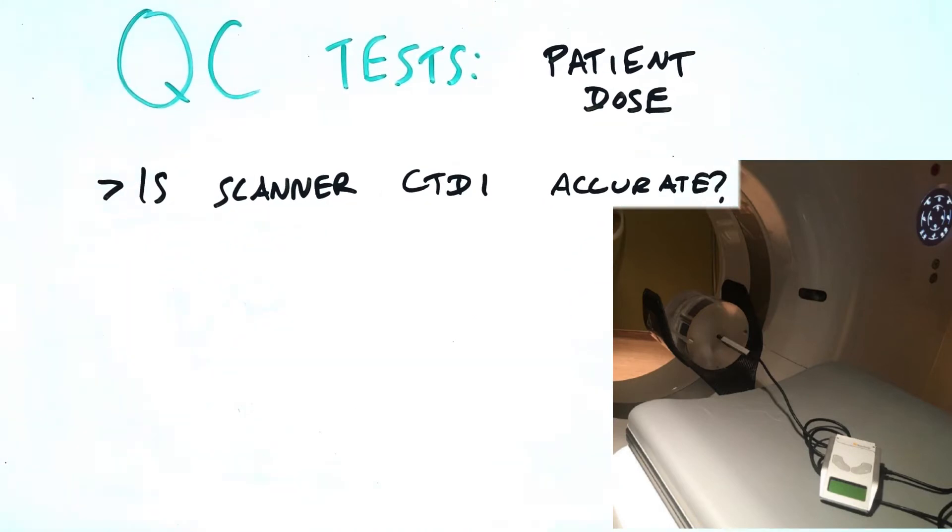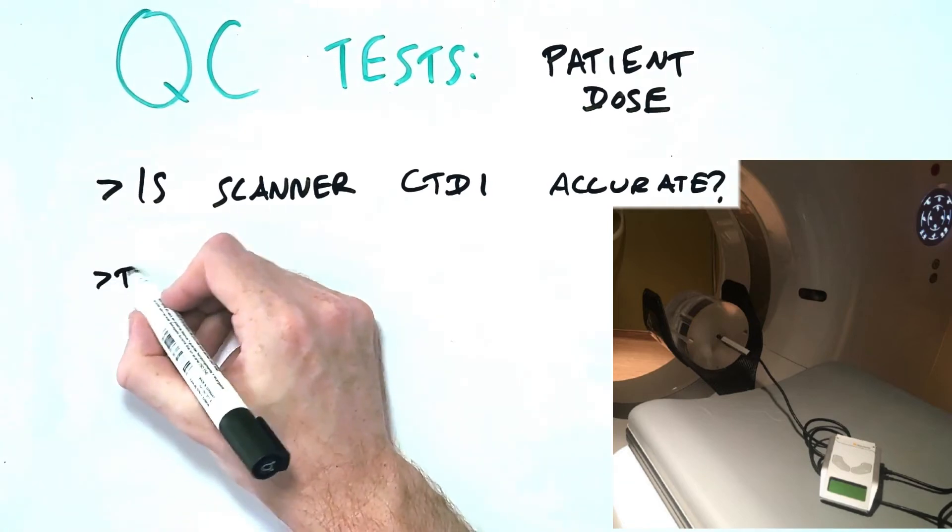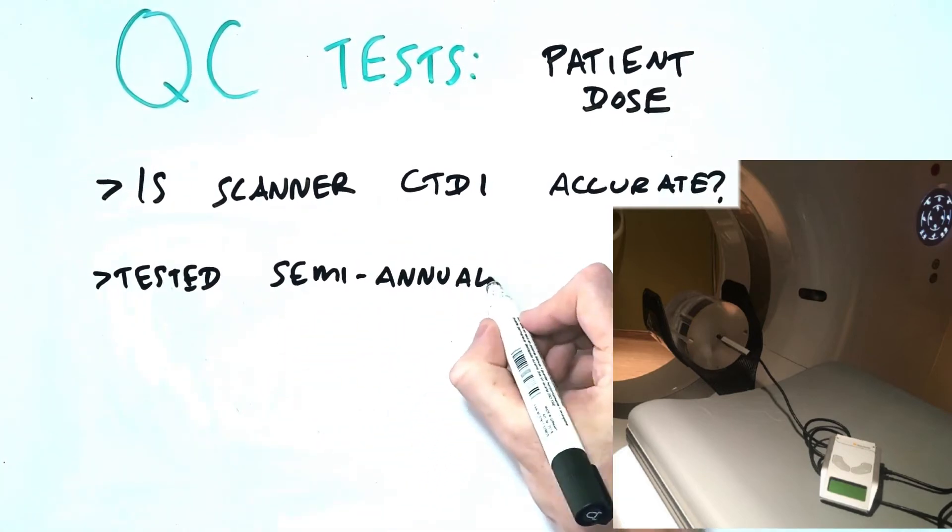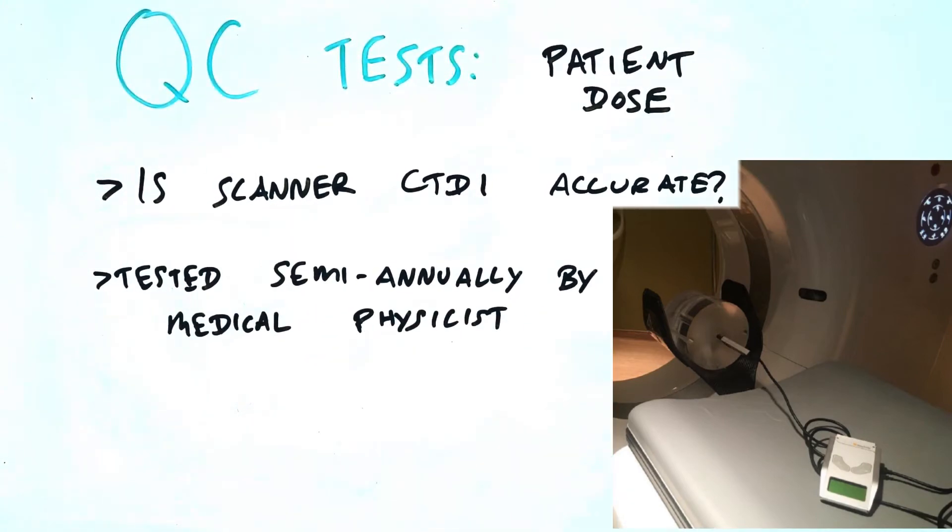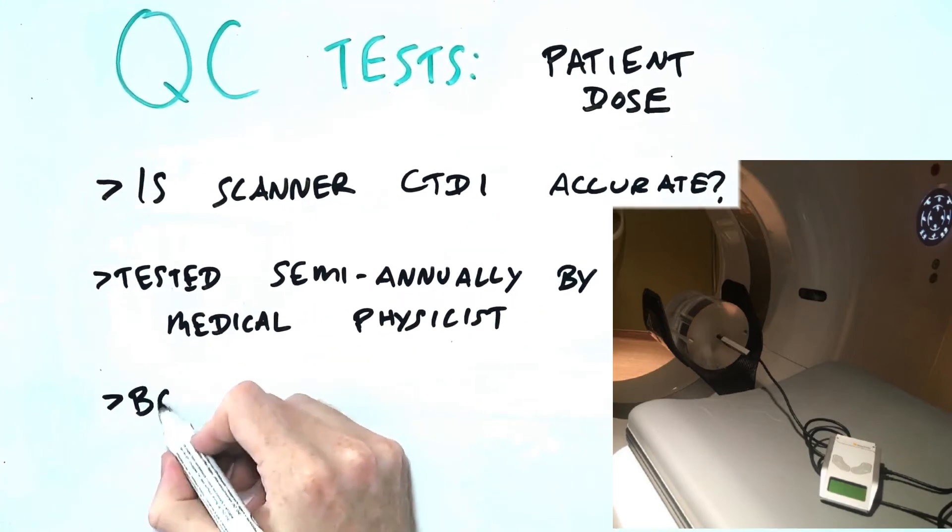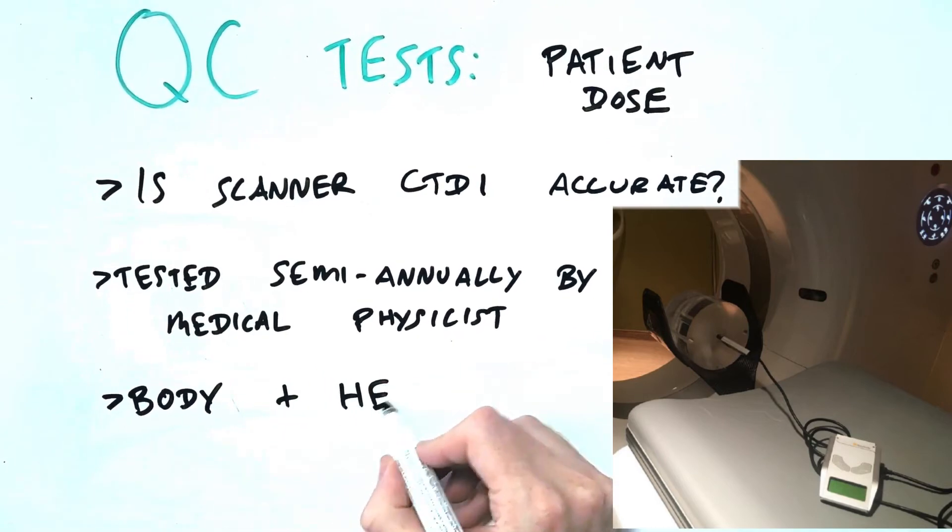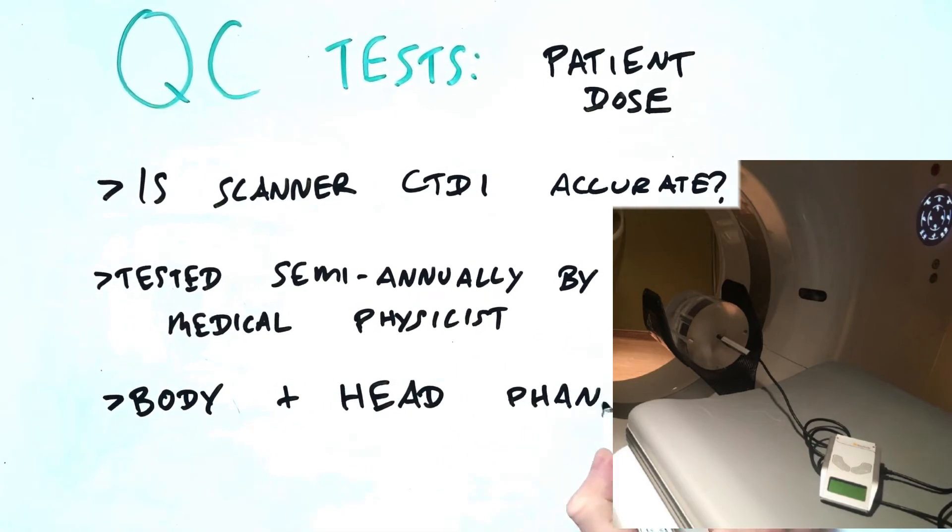As we know, dosimetry is a complex science and it's not always easy to get a true idea of the dose delivered to a patient based solely on the CTDI indicated by the scanner. However, testing this regularly is a good way to ensure that the CTDI displayed is at least somewhat of an accurate representation of what the patient actually received. This should be tested semi-annually by a medical physicist using both a body and head-sized phantom.